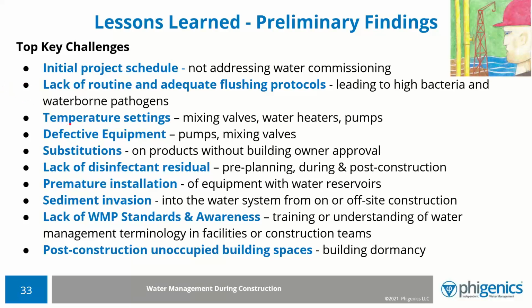Temperatures are often not set, or if they're set at the water heater, no one finds out that it's actually distributing properly—mixing valves and pumps are working. So we end up finding a lot of defective equipment in this process. I'll tell you that 10 to 15% of the equipment in these buildings is defective in these plumbing systems and is not working, even from a performance level. So then you have a water system that's not capable of defending itself from a temperature situation.